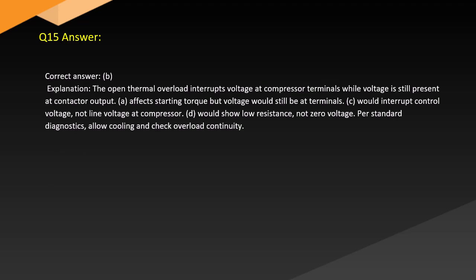Answer. Correct answer: B. Explanation. The open thermal overload interrupts voltage at compressor terminals while voltage is still present at contactor output. A. Affects starting torque, but voltage would still be at terminals. C. Would interrupt control voltage, not line voltage at compressor. D. Would show low resistance, not 0 voltage. Per standard diagnostics, allow cooling and check overload continuity.